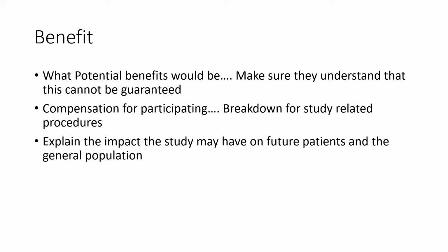You can break it up and say, okay, if you have a medical issue, contact the study doctor or your doctor. If you have an issue with the consent form or feeling like something was not done properly and it's an ethics issue, you contact the IRB. If you have a question about the device, you can contact this person. So break it up, make it specific, and it makes it easier on you, because then the study staff at the site also has that information at their disposal.